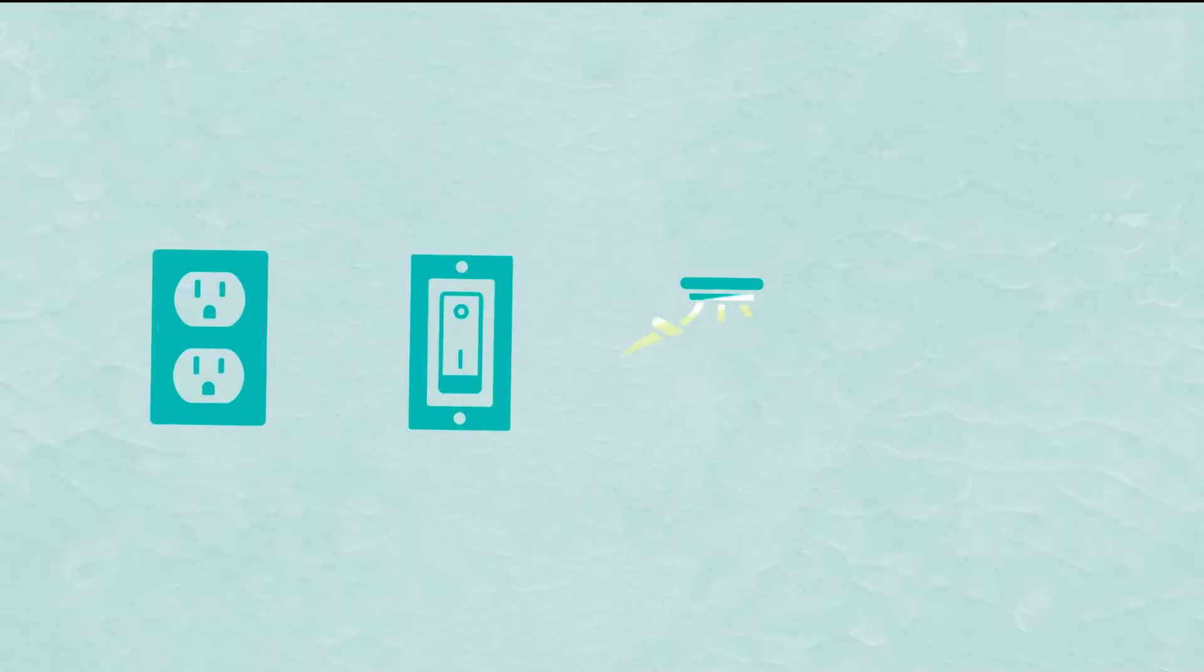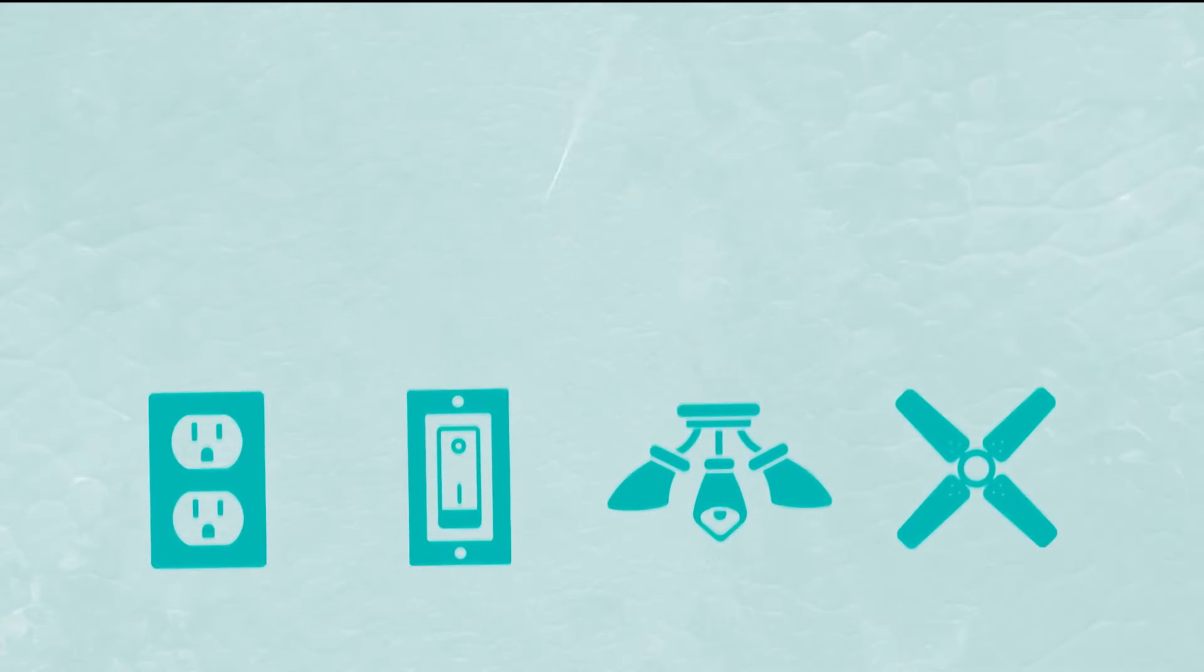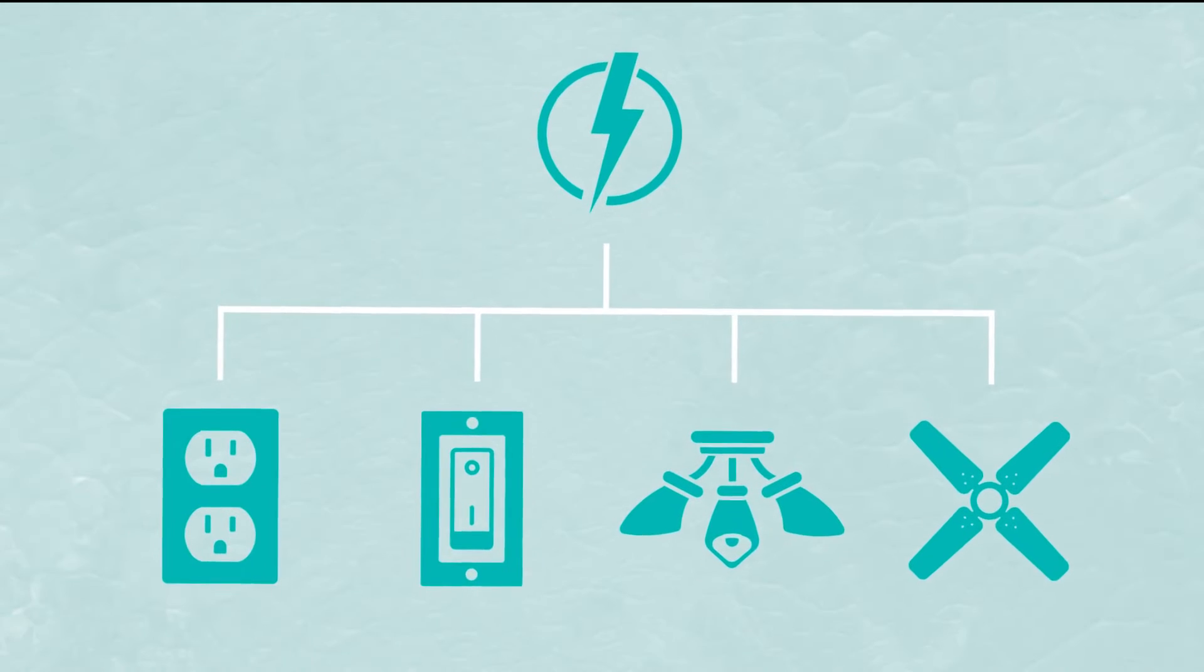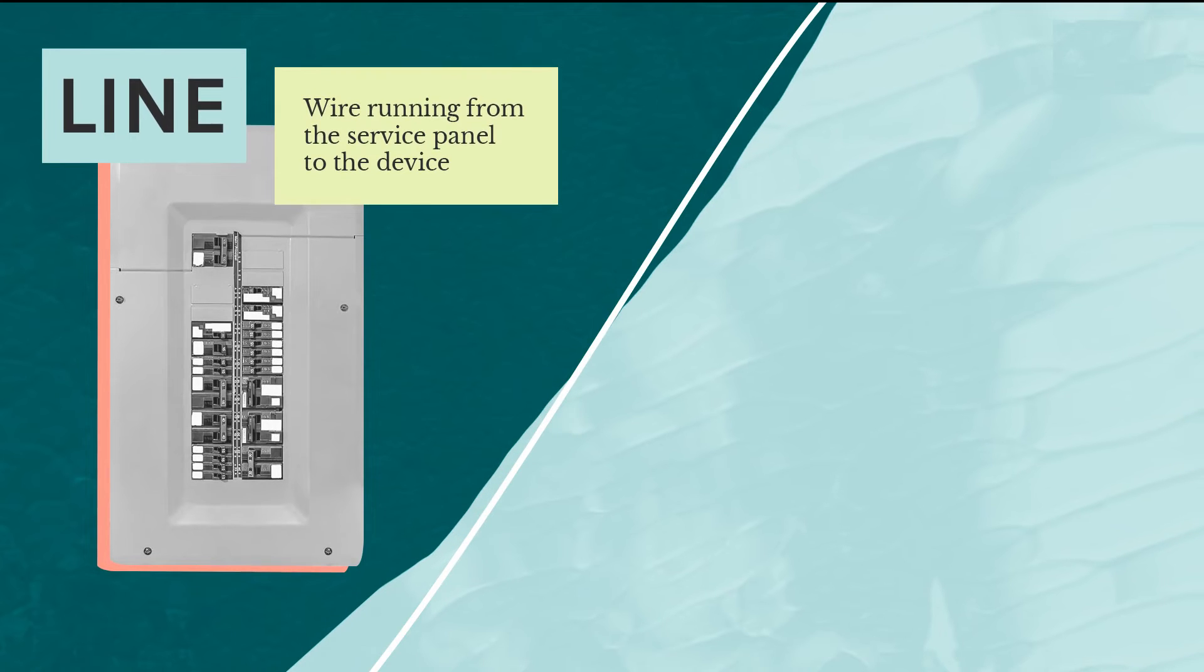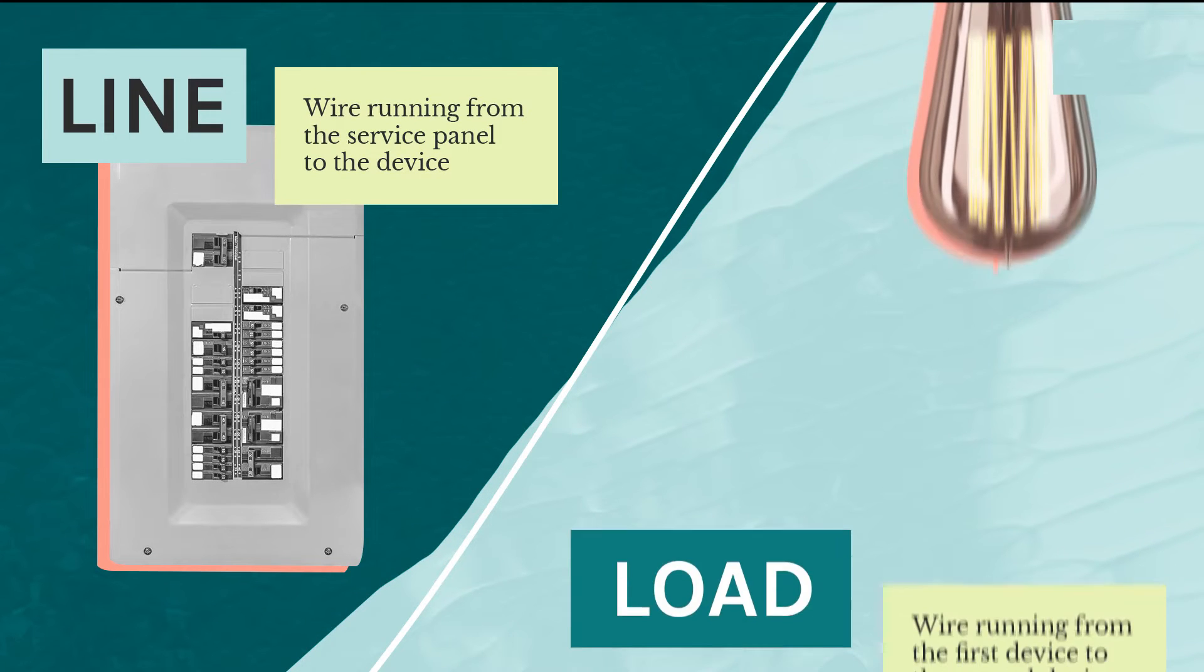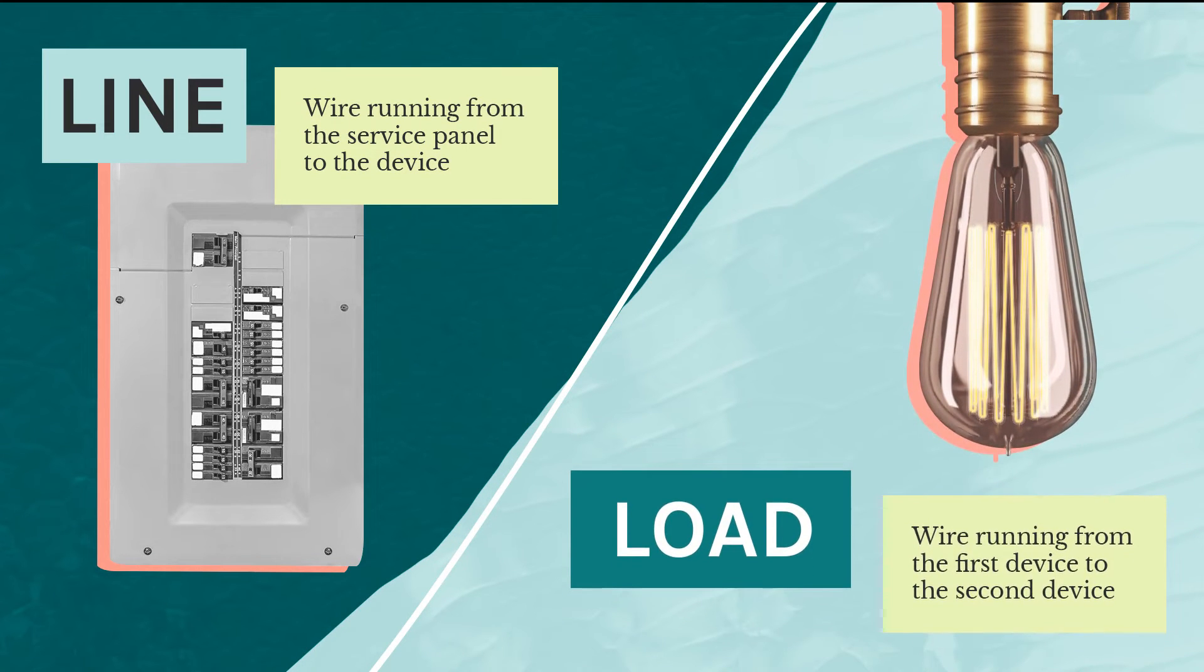Outlets, switches, light fixtures, and other electrical devices are typically wired in multiples on a single circuit. With the first device, the line is the wire running from the service panel to the device, and the load is the wire running from the first device to the second device downstream on the circuit.